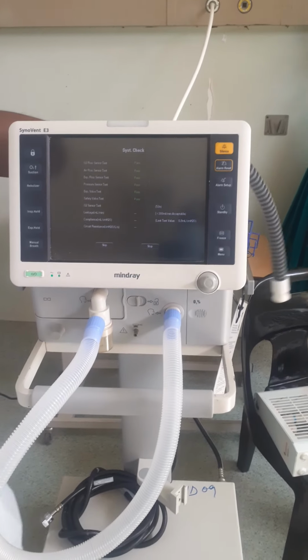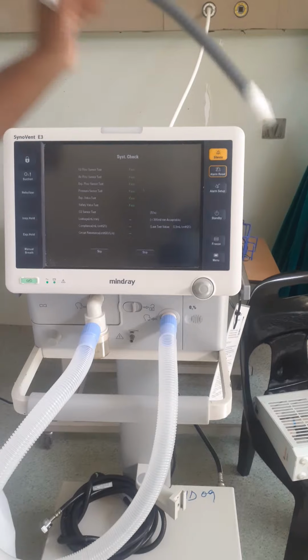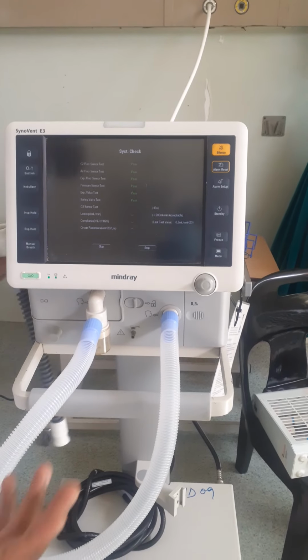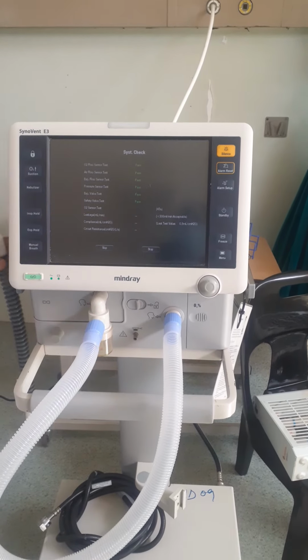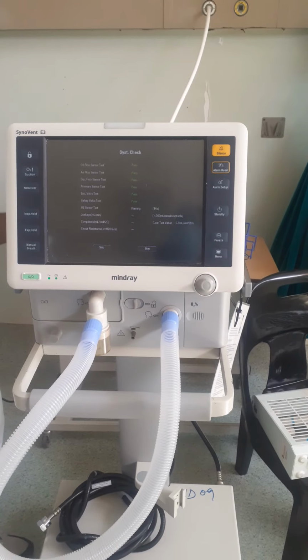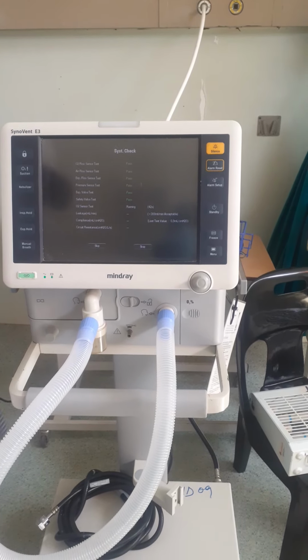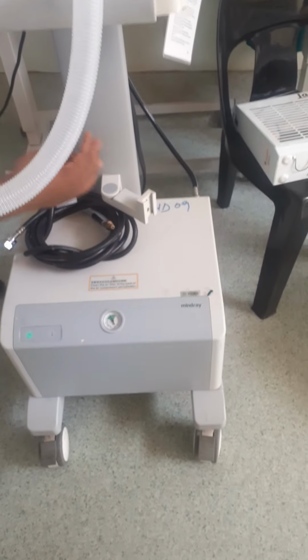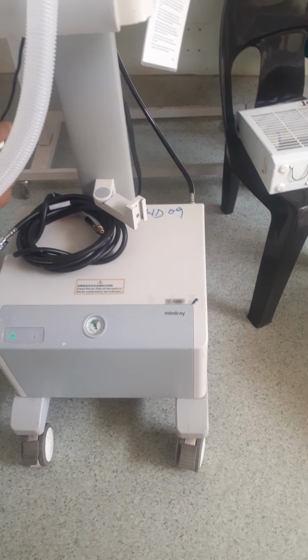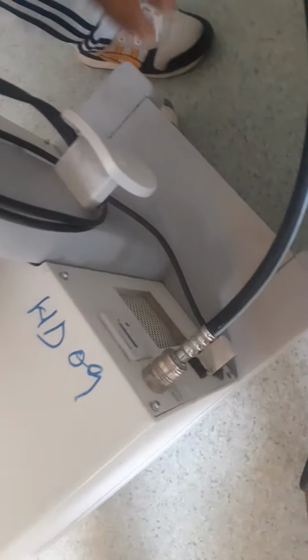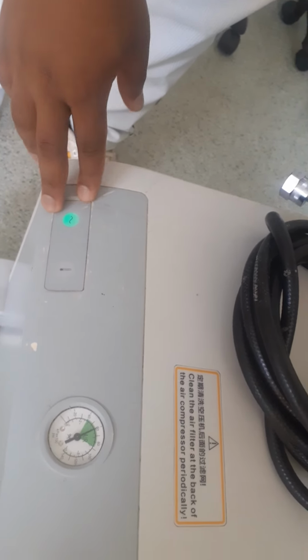Alright, so if there is anything, you should see a failure. As you saw, you don't panic. Whenever there is a failure, you always go back and check what is missing. In our case, we connected our air, but we didn't switch it on. Whenever this switch is on, you will hear a sound or feel a bit of air coming out, so you know that it enters your ventilator. Also, this green light shows that the AC power is on.